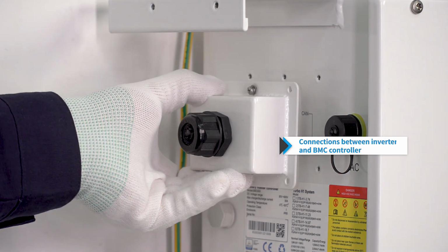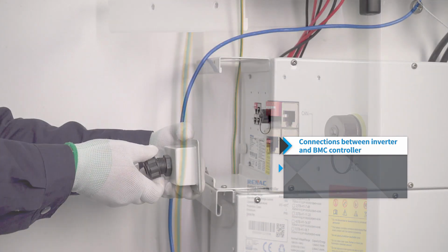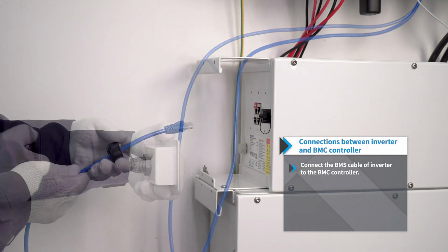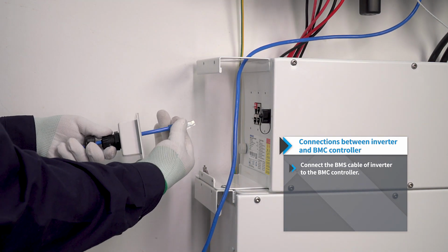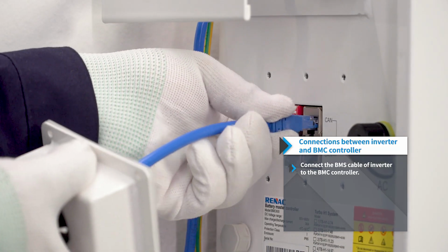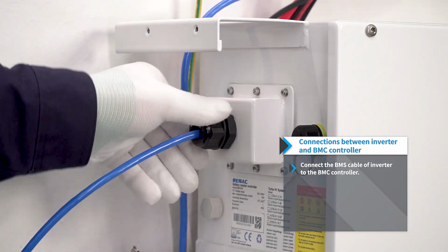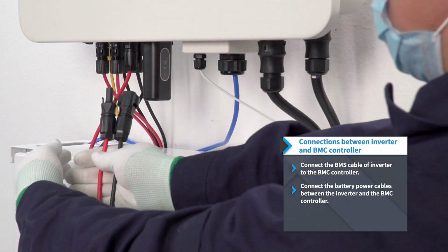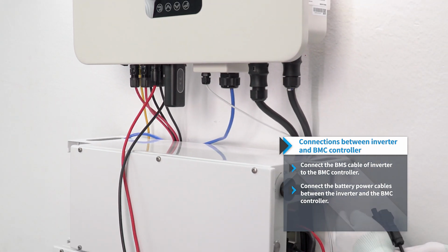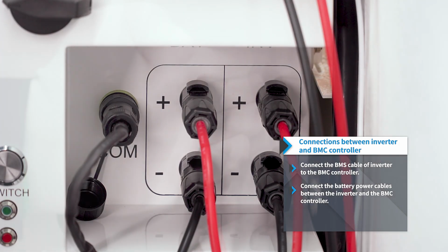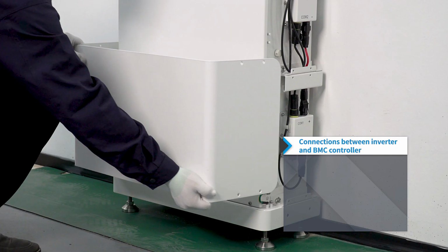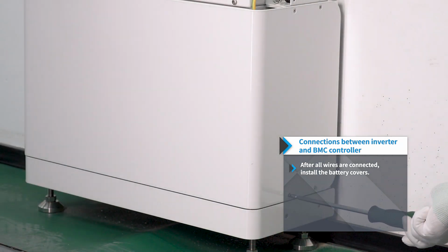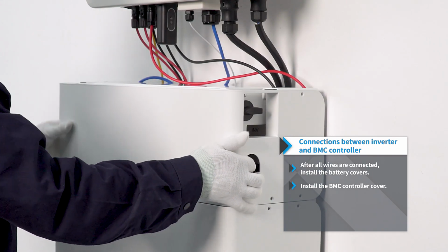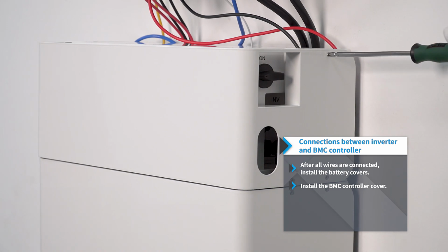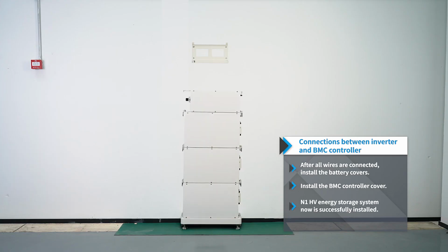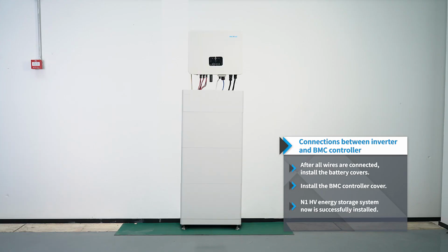Connections between inverter and BMC controller. Connect the BMS cable of inverter to the BMC controller. Connect the battery power cables between the inverter and the BMC controller. After all wires are connected, install the battery covers. Install the BMC controller cover. N1 HV energy storage system now is successfully installed.